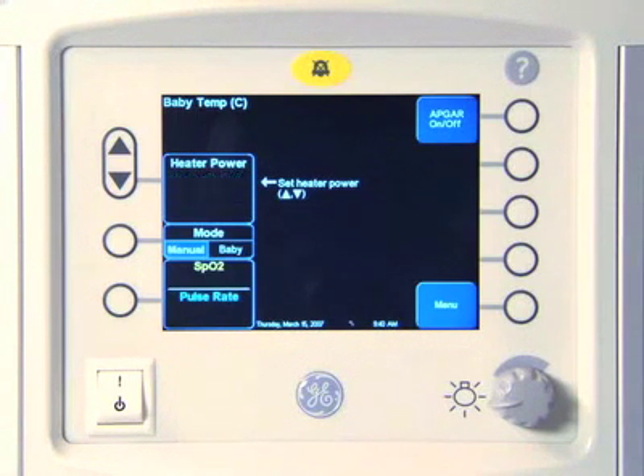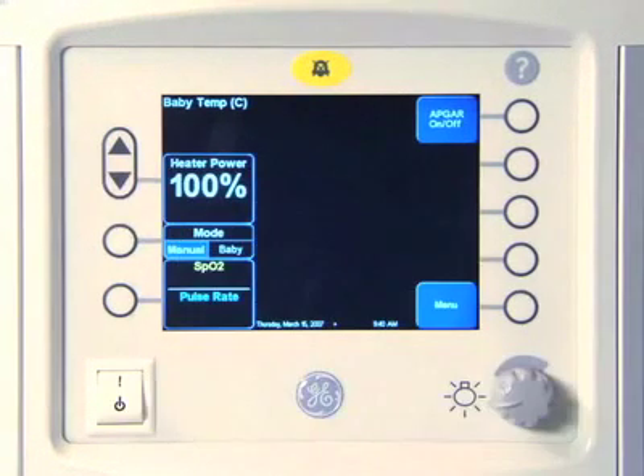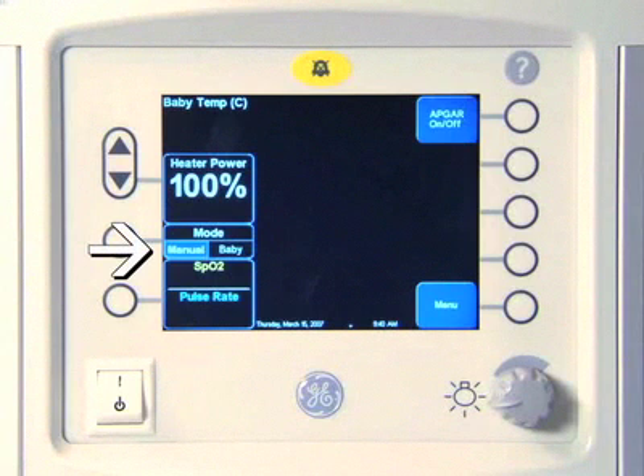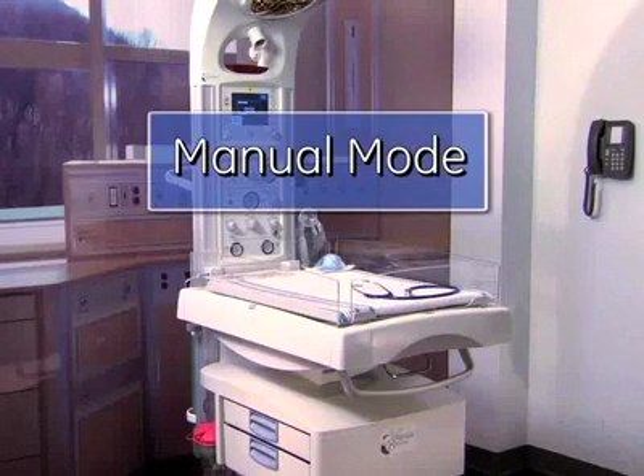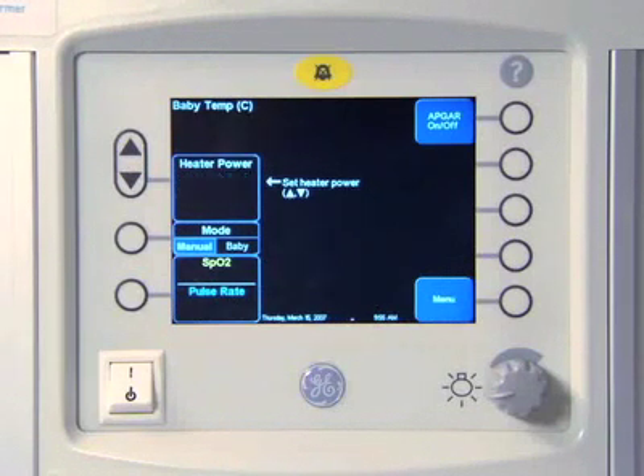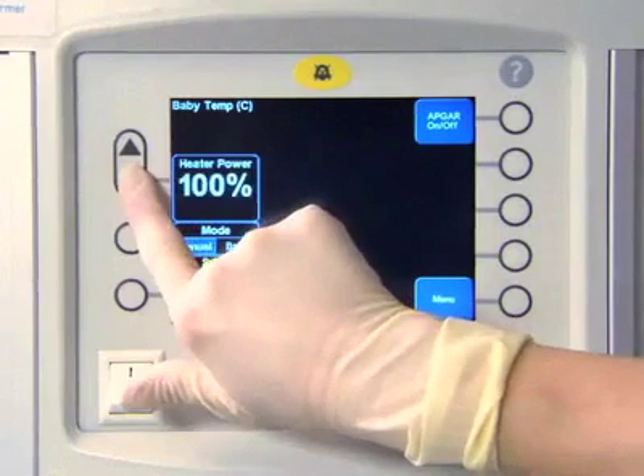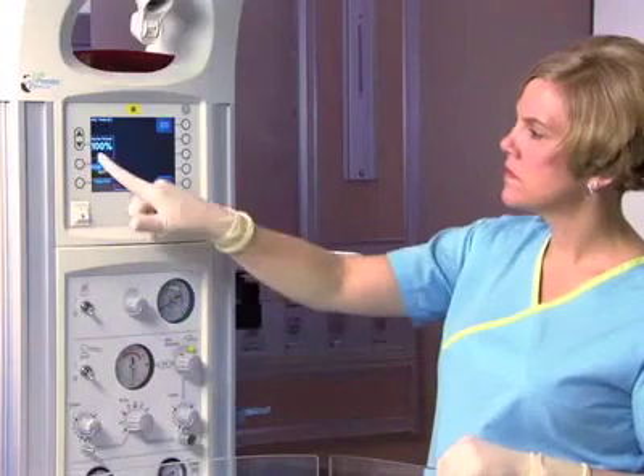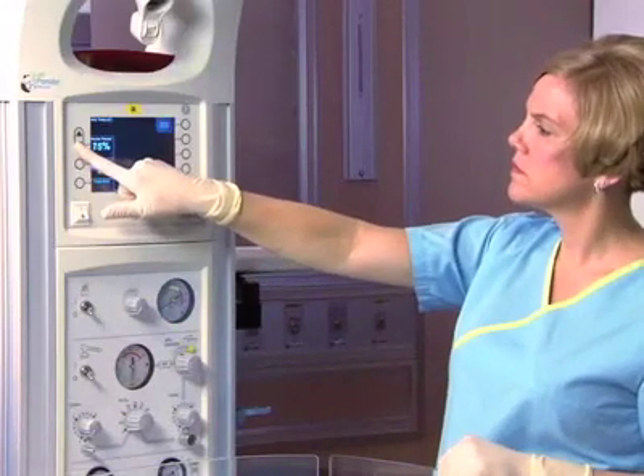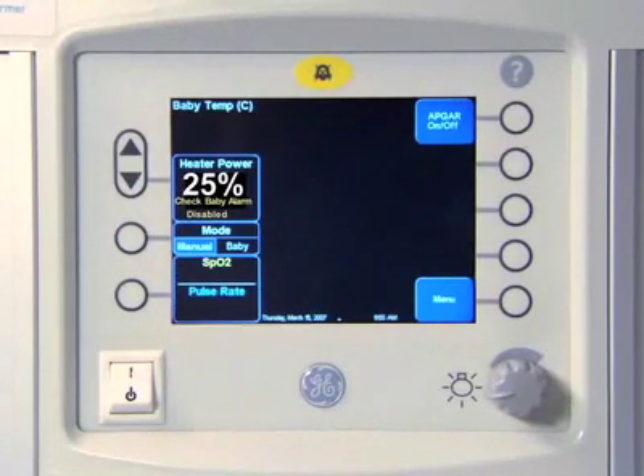Confirm or adjust the heater power setting by pressing the up or down arrows. In manual mode, you will see manual mode highlighted in blue on the control display. Manual mode controls the heater output according to a heater power percentage set by the user. All patient alarms are active in manual mode. Upon entering manual mode, you will be asked to confirm heater power by pressing either the up or down arrow keys. The PandaWarmer is preset so that the check baby alarm is disabled when you select a heater power setting of 25% or below. This may be adjusted at your hospital. Please verify the setting with your manager.